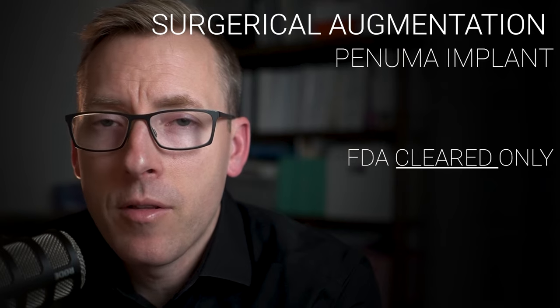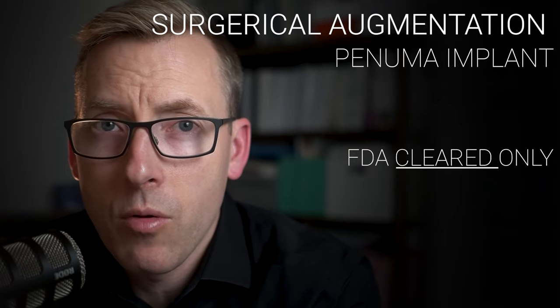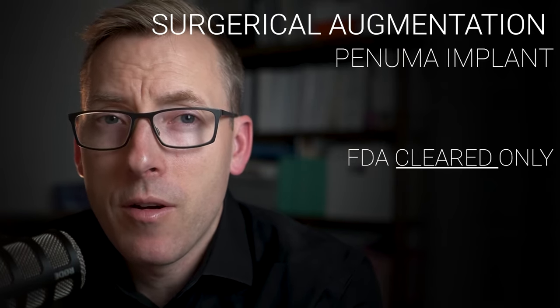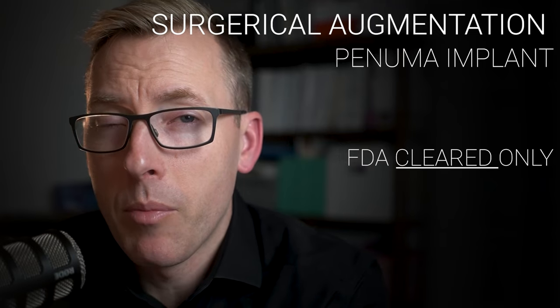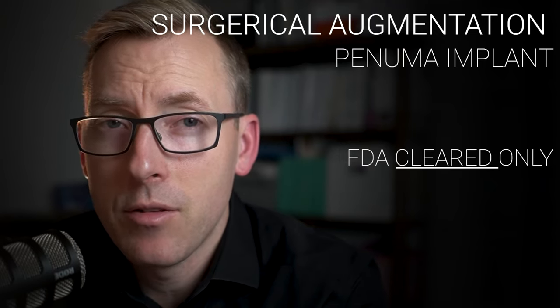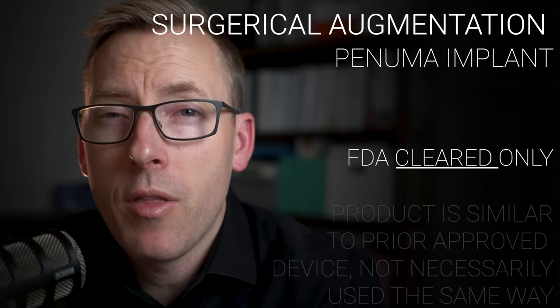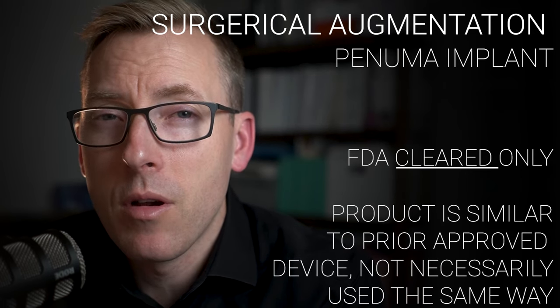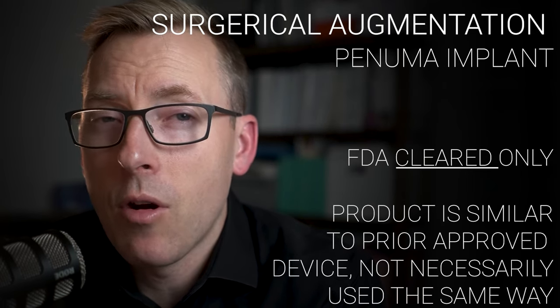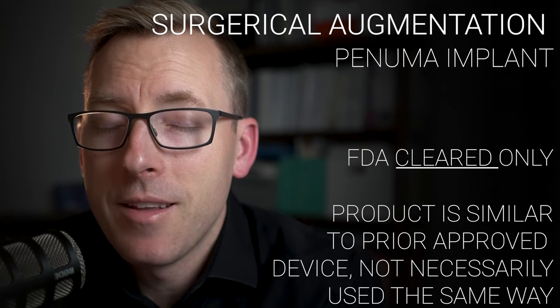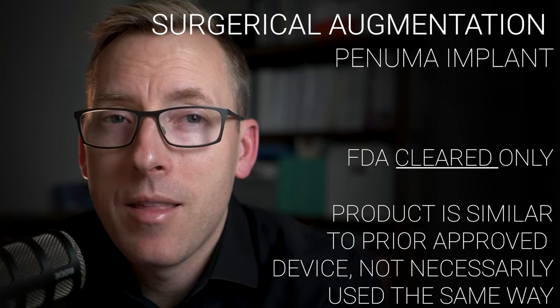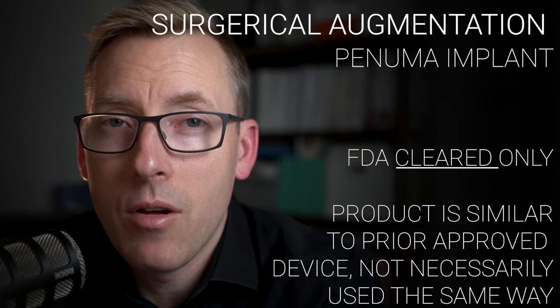However, FDA clearance is a totally different story. To get FDA clearance, the device requires submission of a pre-market notification to the FDA to register the device, showing that it's substantially similar to a product the FDA has already approved. It does not require any safety or efficacy data at all.